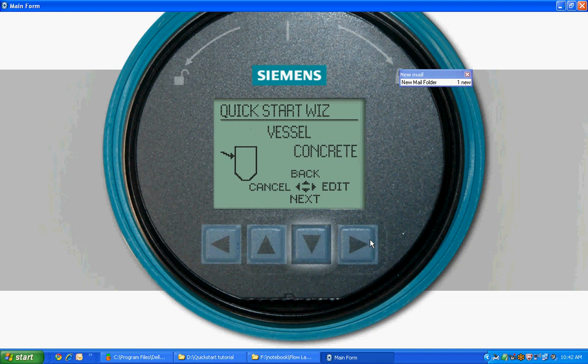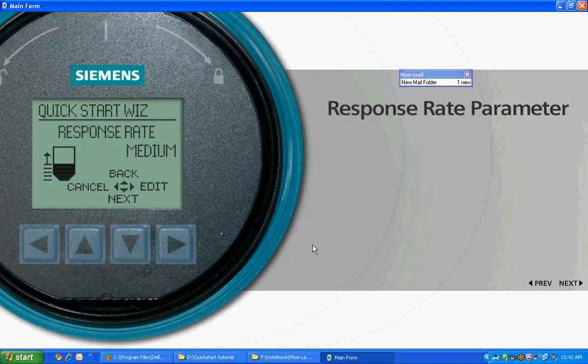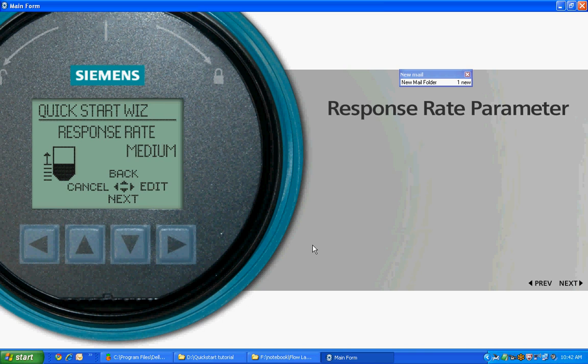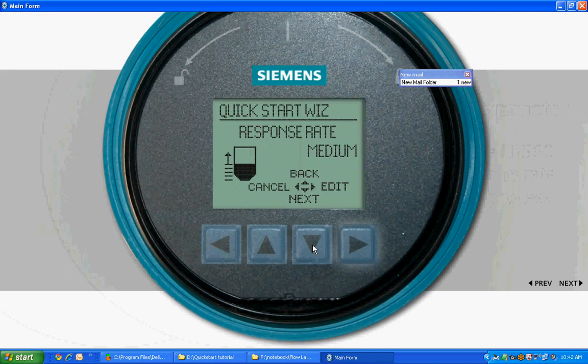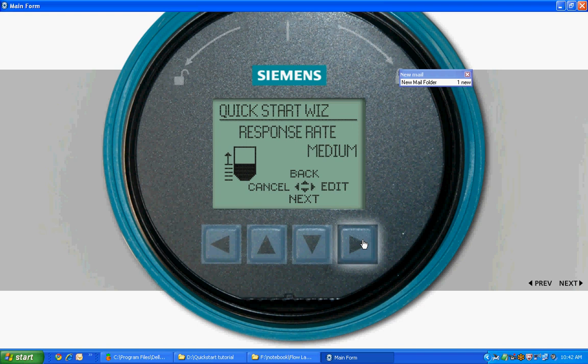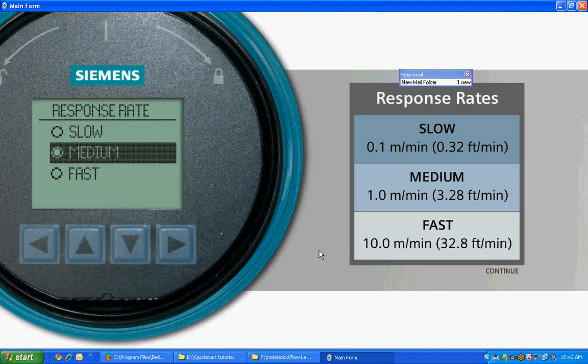Press Next to proceed to the response rate parameter. The response rate parameter is used to match the LR560 reaction speed to the rate of change in the process. Choose Edit to select your response rate. There are three selections for the response rate parameter: slow, medium, or fast. Choose Continue to proceed. Most applications will use the slow setting.